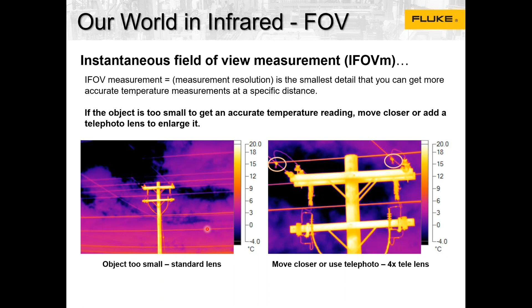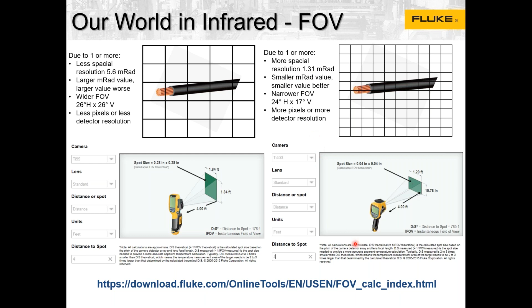This is the FOV, the field of view software. We have the software on our website, so you can go to this link here. This software will allow you to choose the type of camera, what type of lenses, whether standard or other lenses, and what distance you want to measure. And this software will show you the spot size, meaning the smallest spot size that the camera can detect. So this is very important to understand and very important to know.